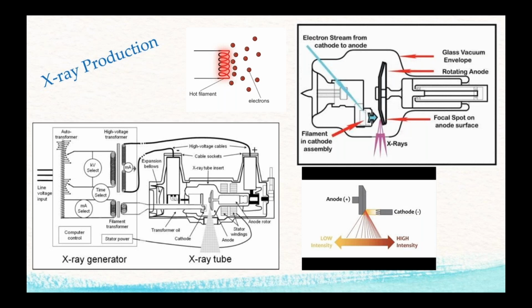Typically, see these in the range of about 24 volts AC, and that's what runs your filament wire, and that's what boils off the electrons. That's called filament. So there's a separate transformer just for that. So we run these high voltage cables out to our X-ray tube. I have an example here. So, you know, this is carrying 75,000 volts on each side up to 150,000 volts across the X-ray tube. So they're normally put in these specially designed ports, and there's only one way that these can fit in. We're going to cover that here after a while.